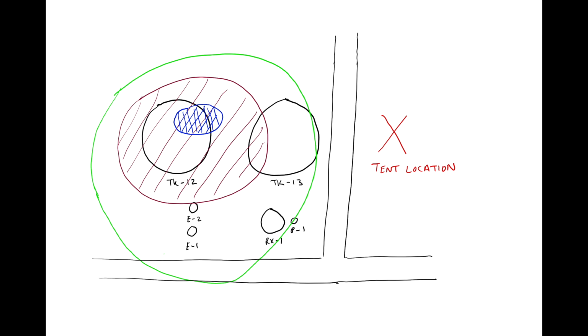If this classification is going across a roadway, like we see when we're looking at our siting issues, as you can see with the green line there, we may want to restrict access to our vehicles and our personnel. And so this is key to do on all of your plot plan drawings for your site, to use them with your electrical classification to determine, are you siting things correctly and are your accesses correct? This also plays into what we talked about with devices. What types of devices are you using in these areas? What types of instrumentation and utility stations are in these areas? So if you do this exercise, this can really help you figure out if all of these things are sited properly.